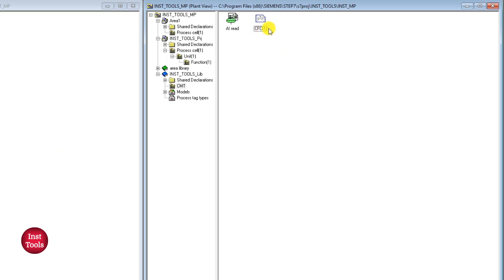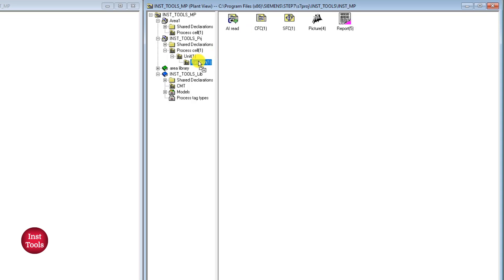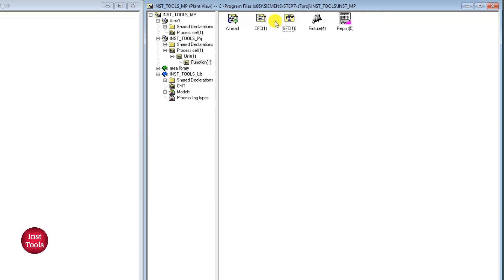Similarly to CMT, we add the I/Os, parameters, and signals here. After adding all parameters, press Finish. The CFC is now turned into a process tag type. To import this process tag type into a project, you can simply drag and drop the process tag type as we did with CMT. There is also another procedure for process tags: right-click, process tags, create an import file.